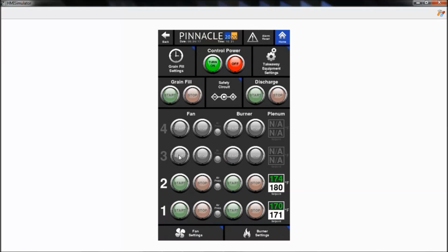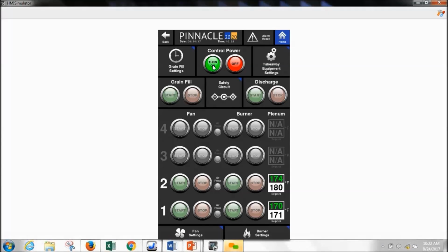When you first arrive at your dryer and have control power turned on, assuming you don't have any alarms, which we'll get into later, your control power screen will look like this. You can see several different buttons and shades. One shade we talked about already is this grayed out button, which indicates a feature that's not installed on the dryer - all the text is gray, and any fields will say not available. That indicates the feature is either not associated with that model dryer or isn't installed on that machine. We can also see buttons like these that aren't completely gray - they're dimly glowing green and red, but not fully illuminated. That tells us these components are installed on the machine but can't currently be turned on for one reason or another. Then we have these control power buttons at the top, illuminated green and red, telling you they're currently ready to be activated.